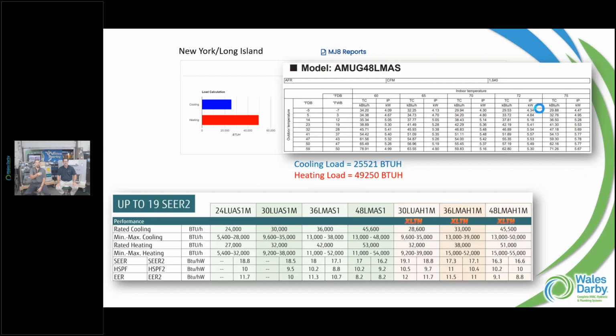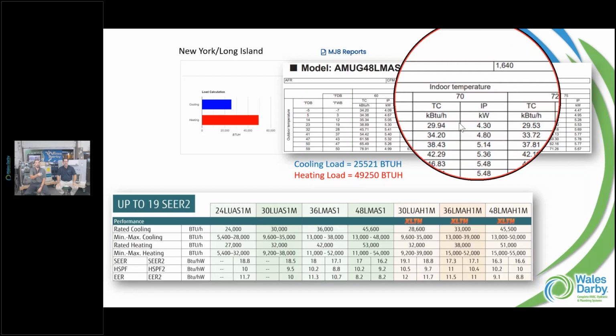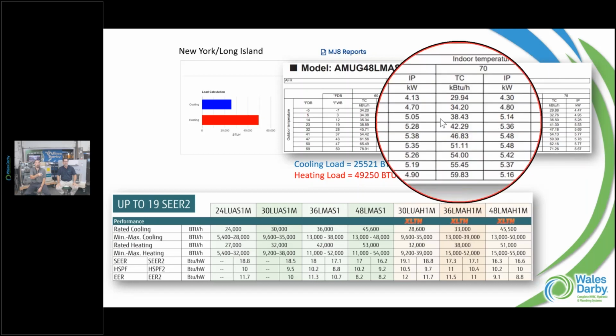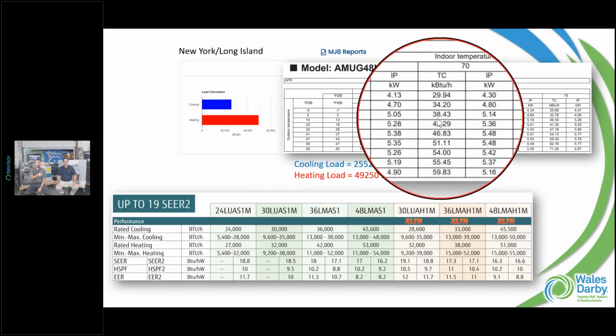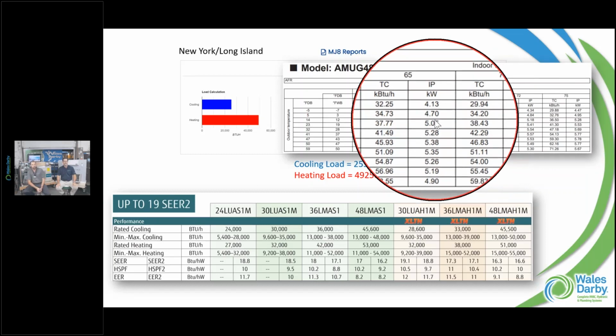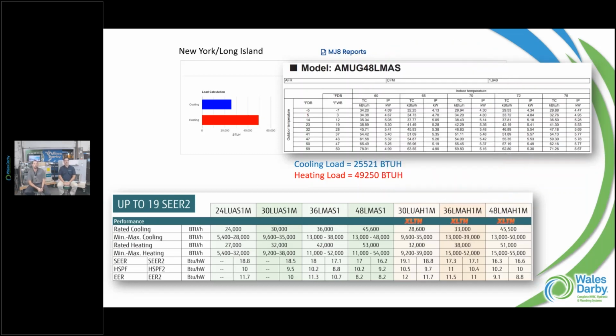If I go to my 70, there's a little delay on the pointer, but in the third row down you can see I'm getting about 38,000 BTUs on a 15-degree day. With that 38,000, I'm 10,000 short of my total load. That total load is for the worst possible day, what we call our design day. So I'm short 10,000 BTUs. Can I cover the full load with this piece of equipment? No, I can't.